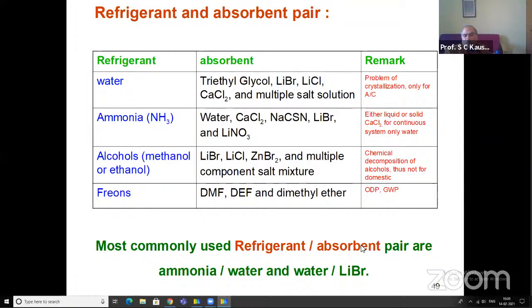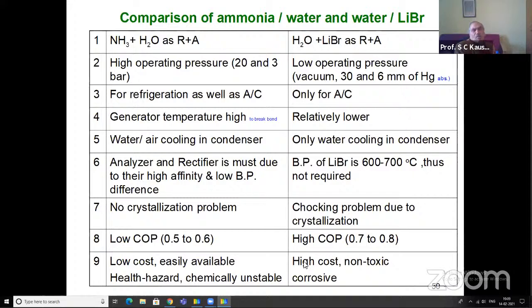Most commonly used refrigerant absorbent pairs are ammonia water and water lithium bromide, which are commercially available vapor absorption systems. In India, Thermex manufactures vapor absorption systems based on these combinations as well. Now we have a comparison of these two combinations, because these are the two options most suitable for vapor absorption systems, and we have to see their relative merits and demerits. In the ammonia water case, ammonia is the refrigerant and water is the absorbent. In the water lithium bromide case, water is the refrigerant and lithium bromide is the absorbent.